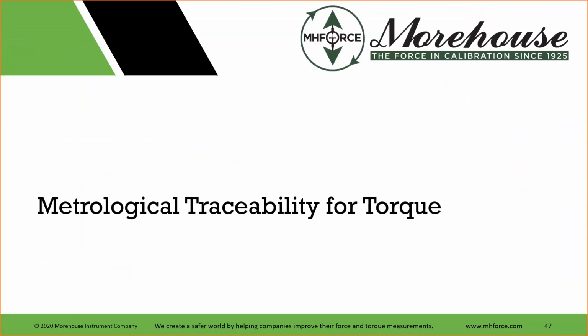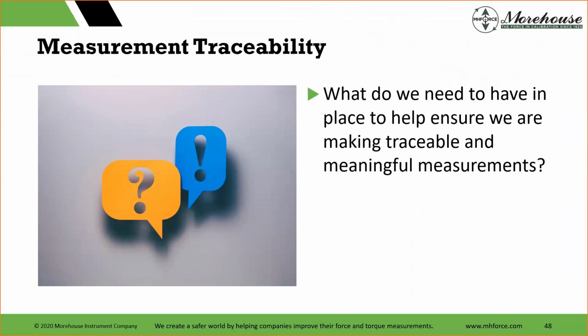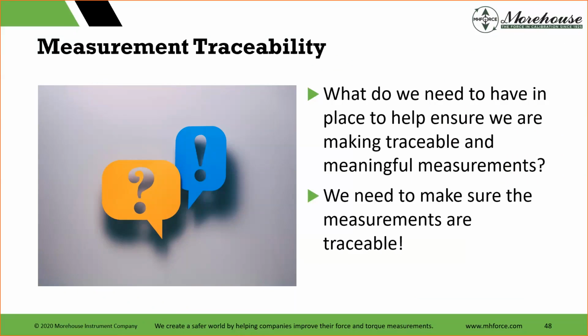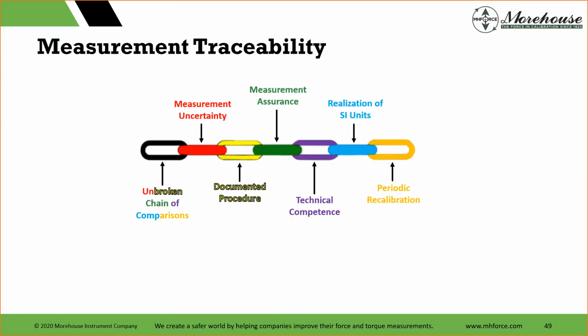Now we're going to discuss metrological traceability for torque. And what do we need to have in place to help ensure we are making traceable and meaningful measurements? And I have to say here, this can be applied to everything, right? Not only torque, it can be applied to force, pressure, whatever disciplines you're in. So we need to make sure the measurements are traceable. So what we're looking at here is first, we're looking at a chain. I like to call this the measurement traceability chain.